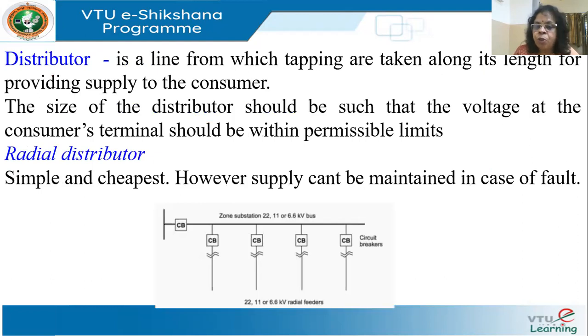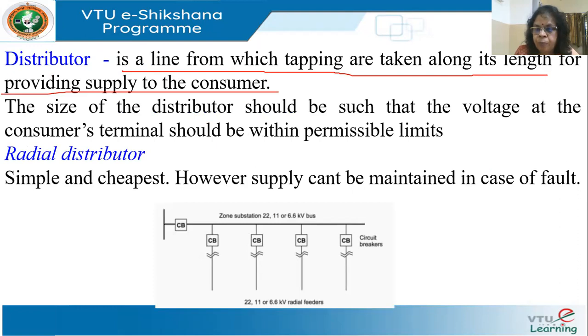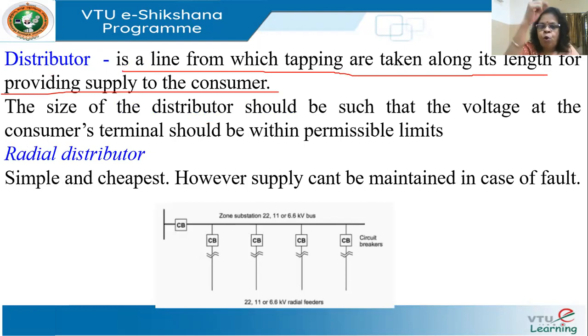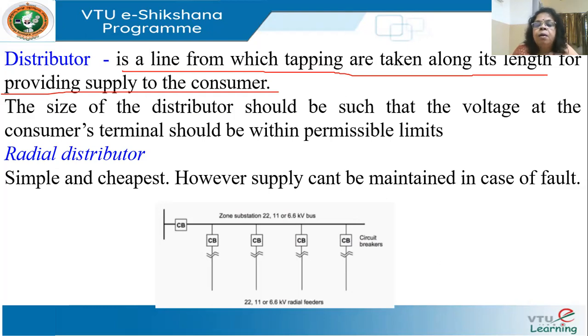Next we have distributors. A distributor is a line from which tappings are taken along its length for providing power to the customer. From your local transformer, a conductor runs and is tapped and given to local poles. That is the fine distinction between a distributor and a feeder, though these two terms are often used interchangeably.